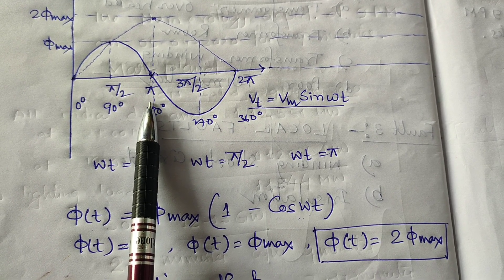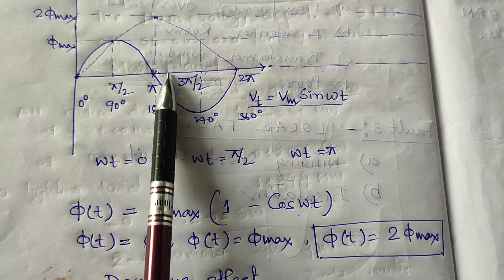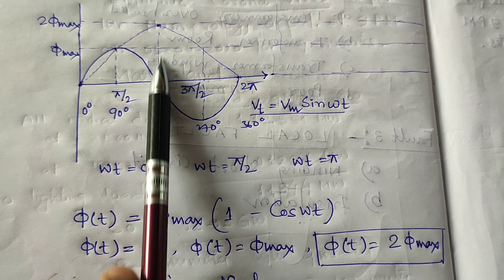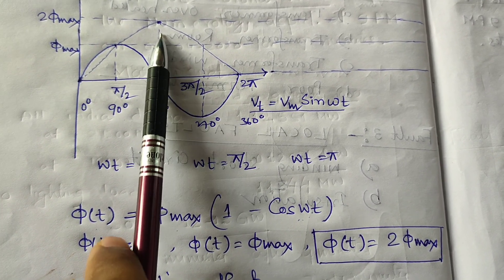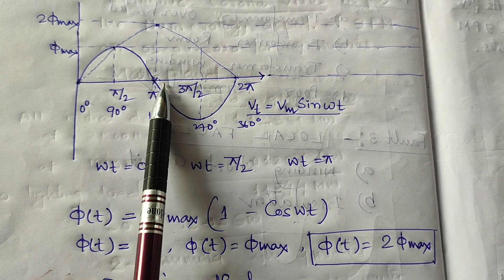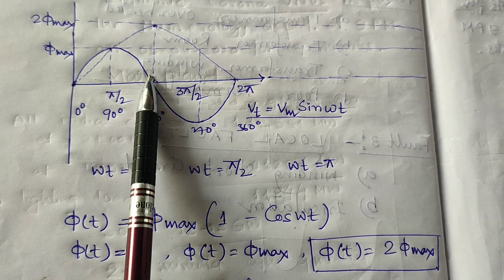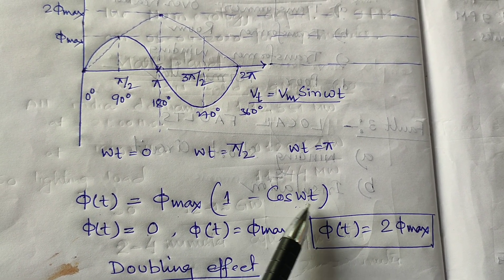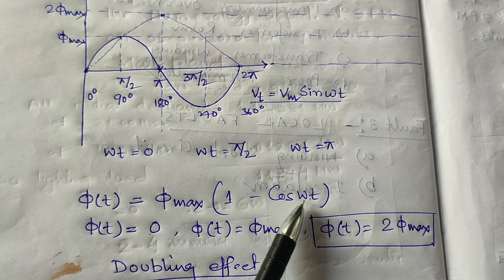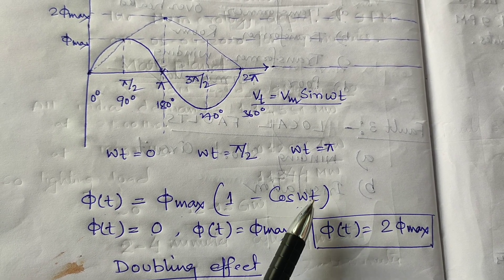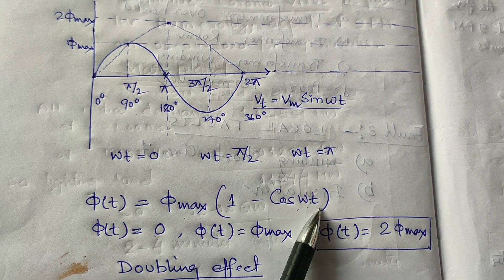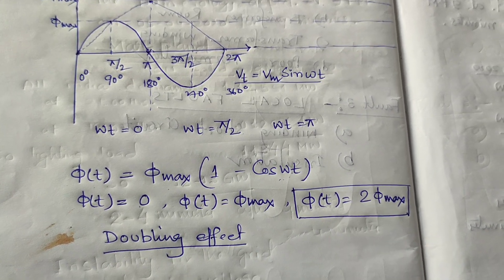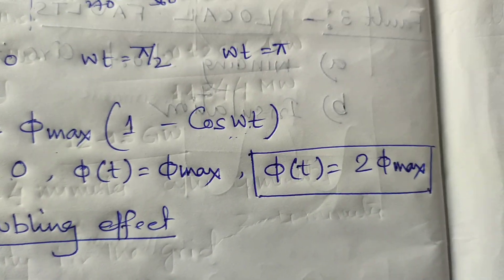This 2φmax value represents the inrush current condition — a huge amount of current is required to saturate the transformer core. Using φ(t) = φmax(1 − cosωt), at ωt = 180°, cos(180°) = −1, giving φ(t) = φmax(1 − (−1)) = 2φmax. So we get 2φmax, which drives the inrush current in the transformer.